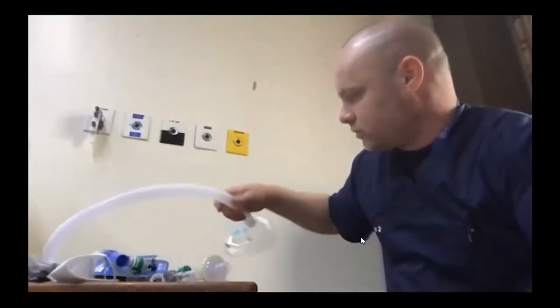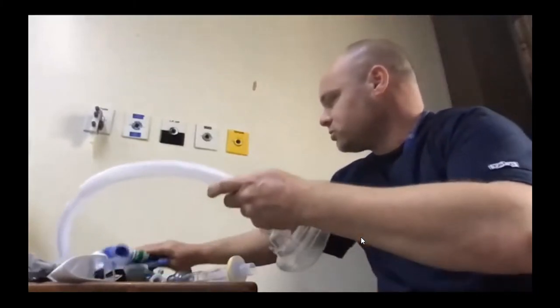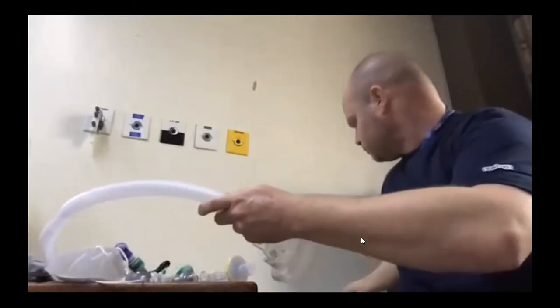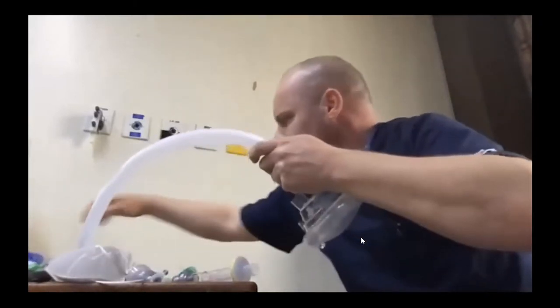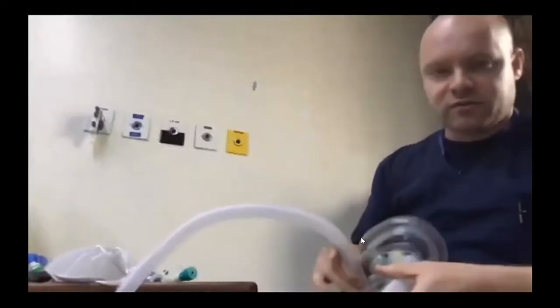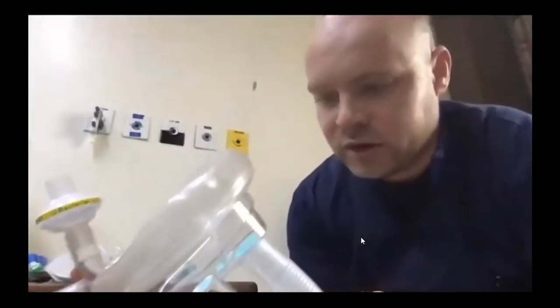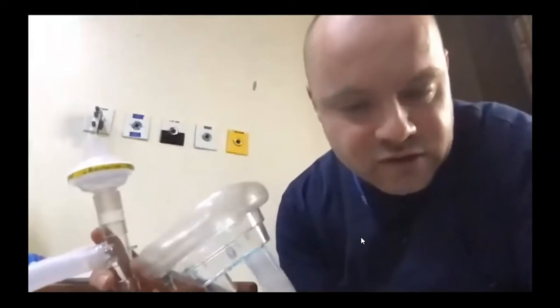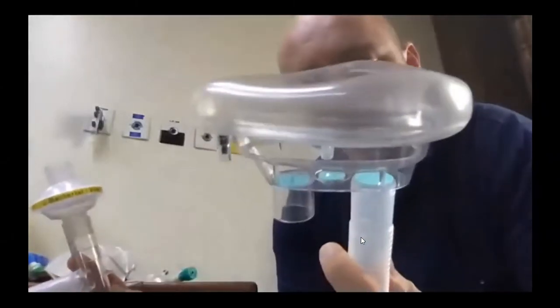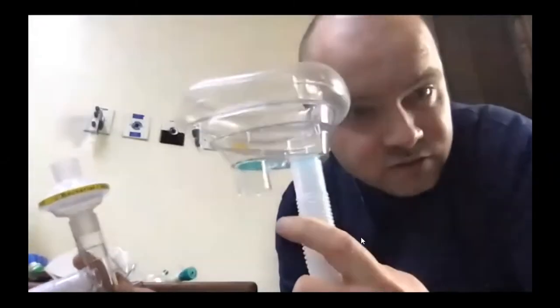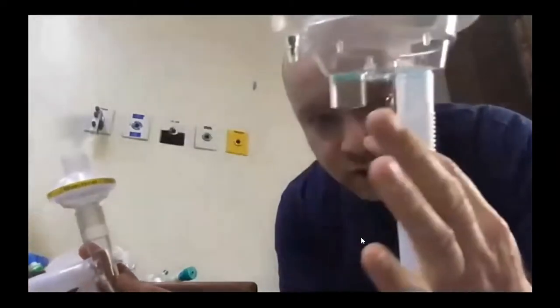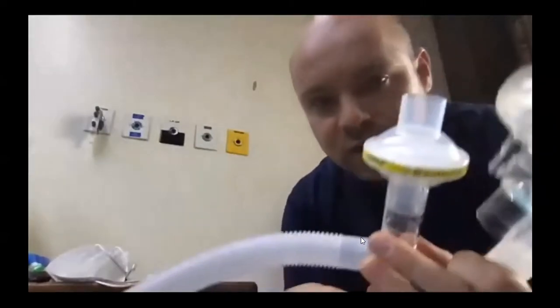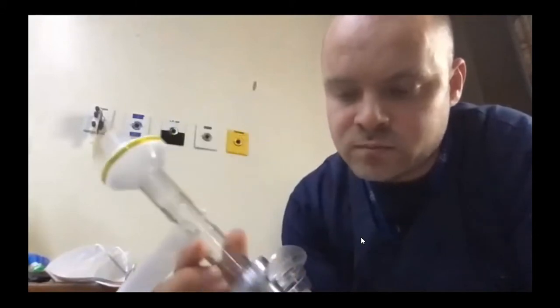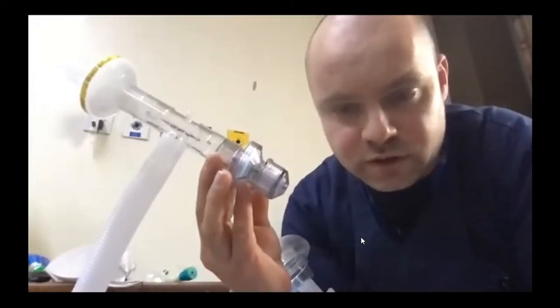As far as circuits, we've got two pretty much to go through here. I've got the one provided with the device that you would have gotten. So this is pretty much an exact setup as UCL had. It's a dual port mask with an anti-asphyxia valve mounted in it. Standard 22 mil hosing, viral filter on the inlet, just to make sure your entrained air is pretty clean. And this is then the pressure relief valve.